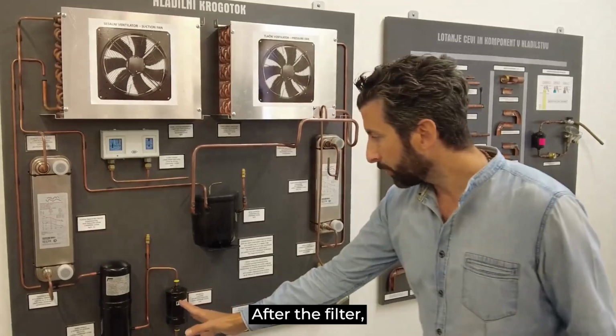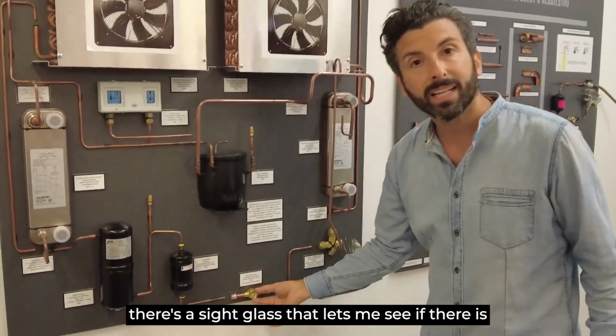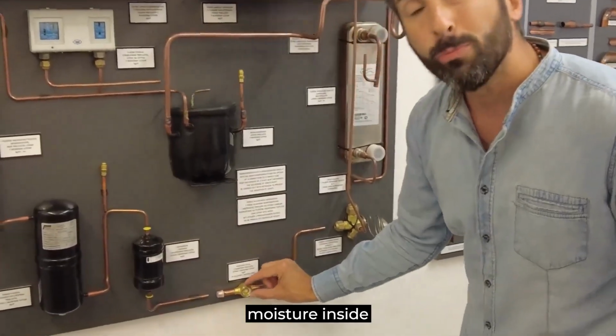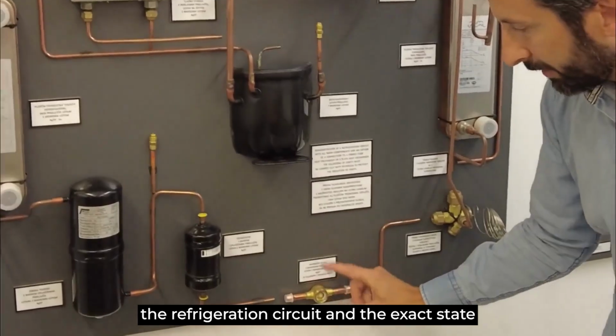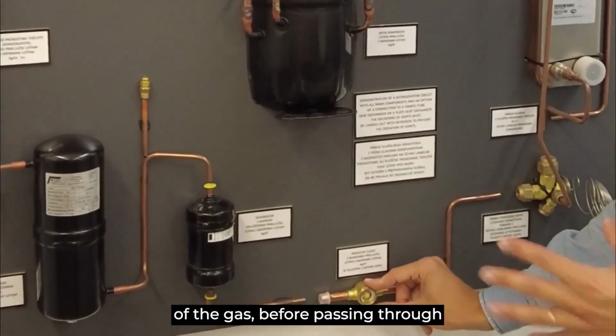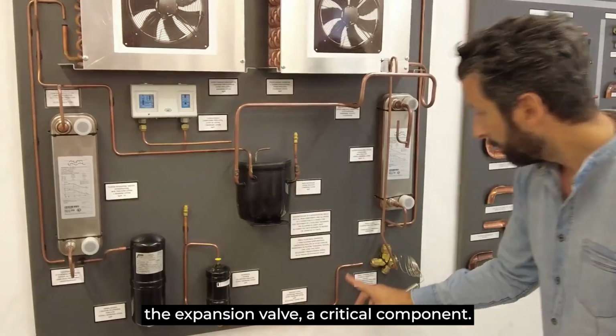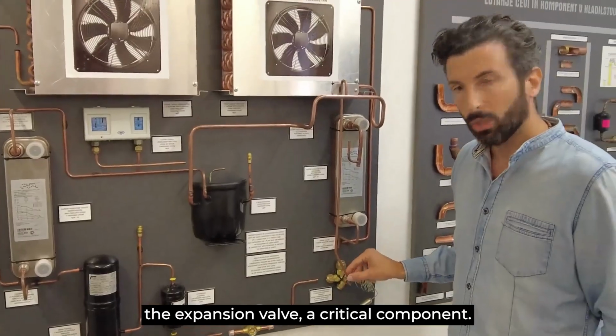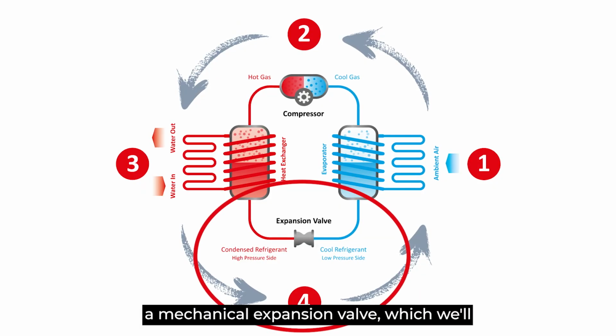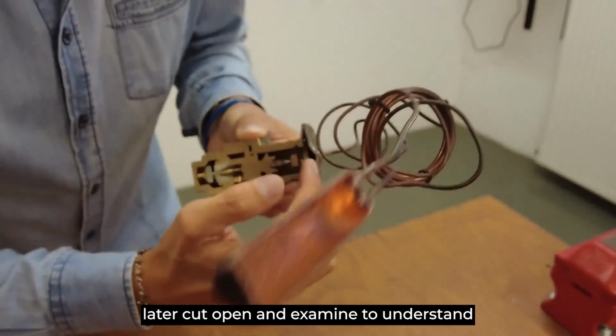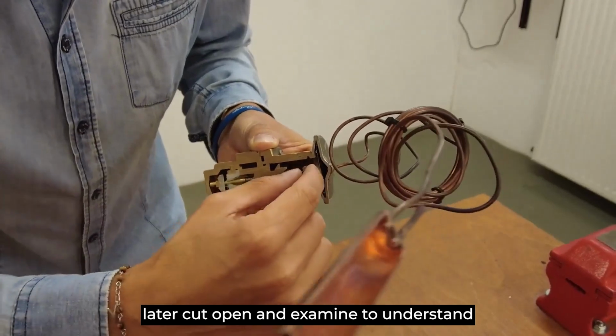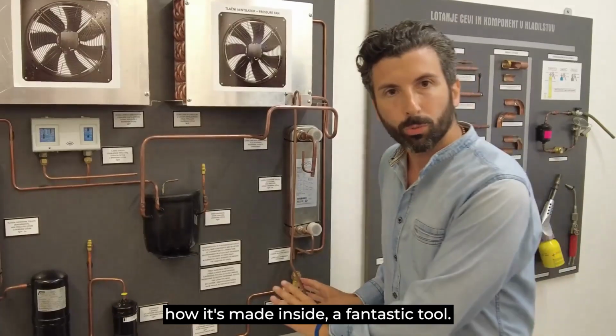After the filter, there's a sight glass that lets me see if there is moisture inside the refrigeration circuit and the exact state of the gas before passing through the expansion valve, a critical component. In this case, we have a mechanical expansion valve, which we will later cut open to examine to understand how it's made inside, a fantastic tool.